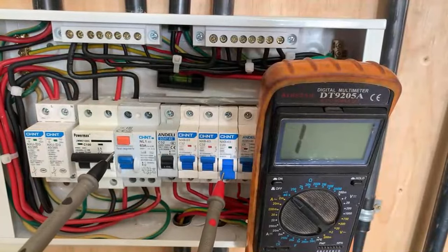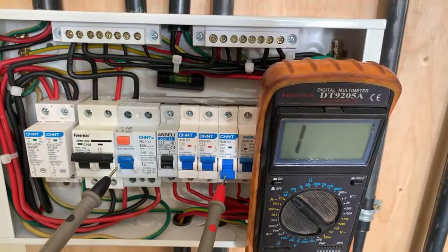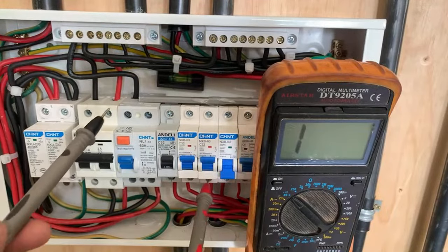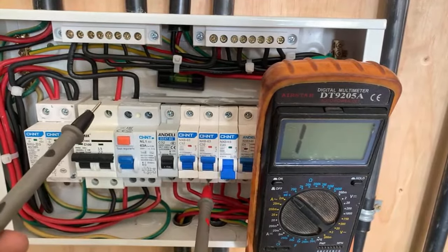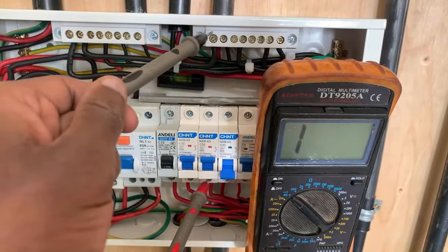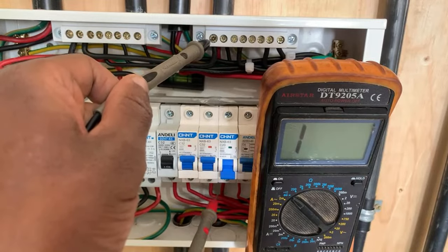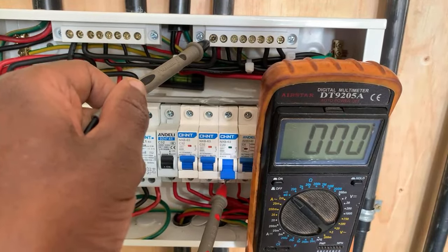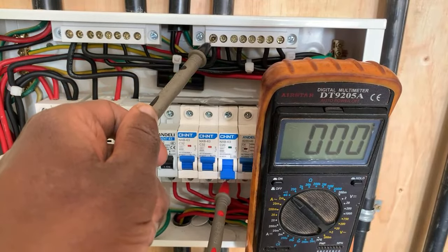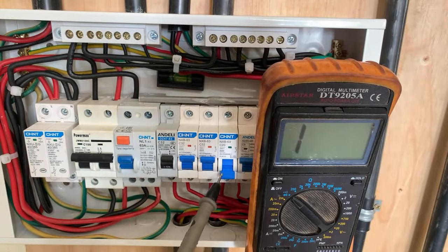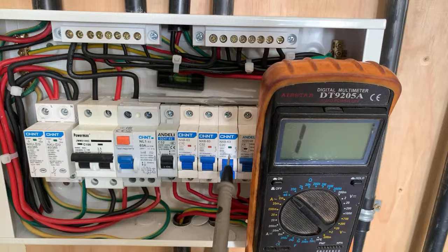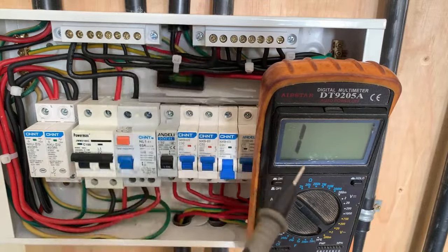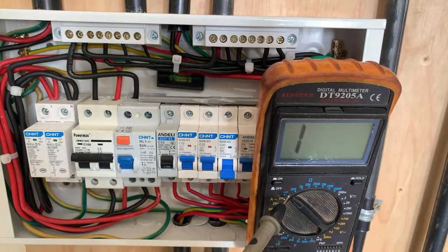So this is the breaker which has an issue, or the circuit that has a problem. I simply place it, mark you, where I'm placing it is on the output. So meaning I'm determining whether the circuit has a short. I will place it there, and also on that one, there we go. That circuit has an issue. So if you go ahead and raise this circuit breaker, it will still trip. There will still be a lot of sparking here, because you are forcing the circuit breaker to operate under a fault.